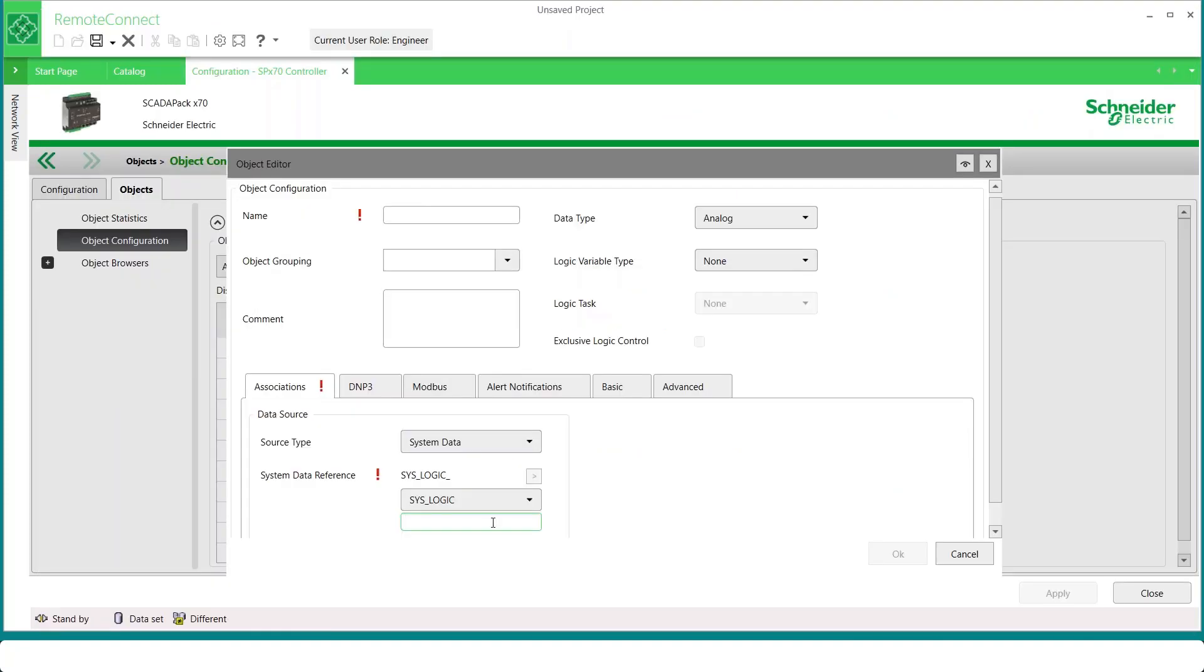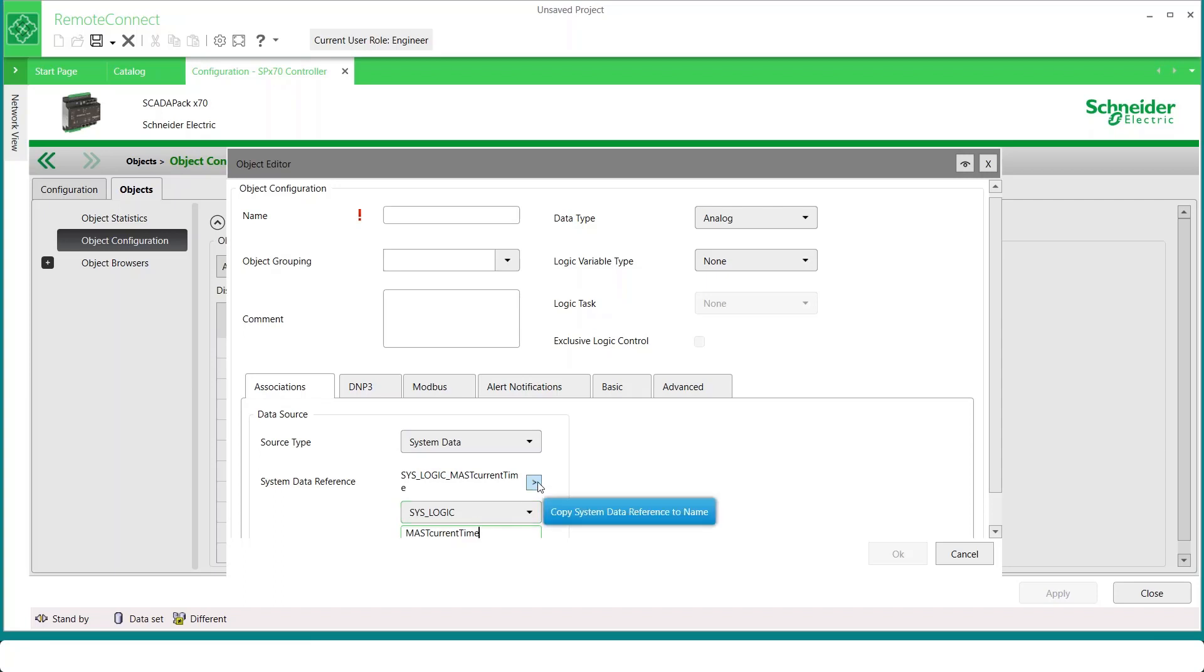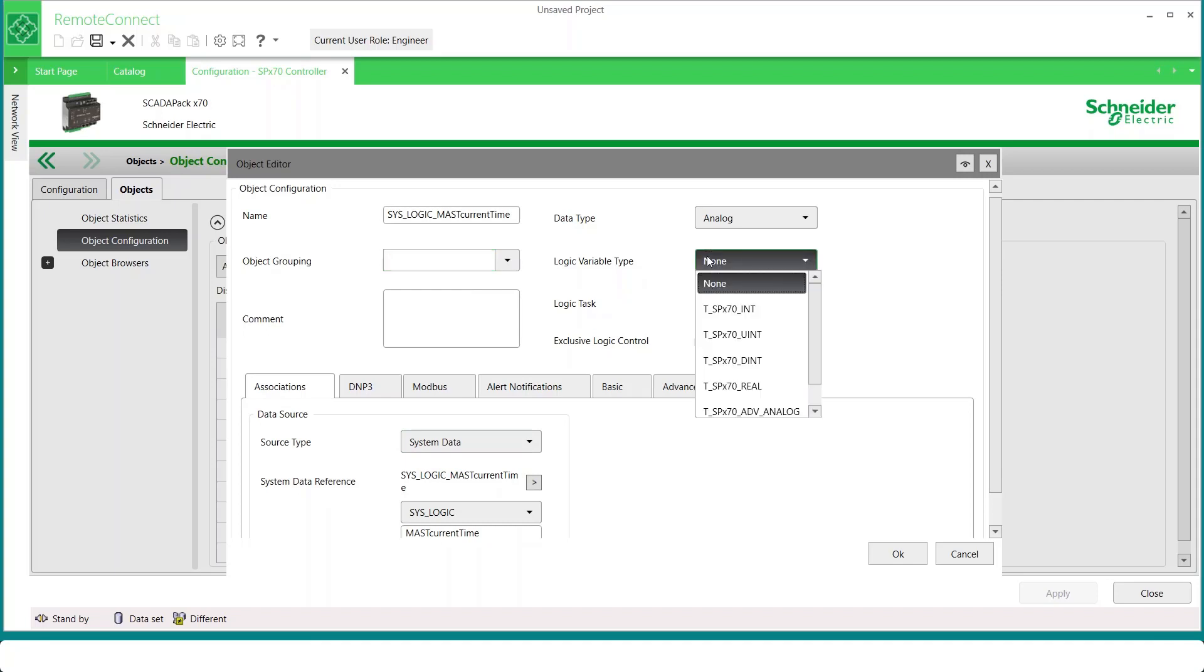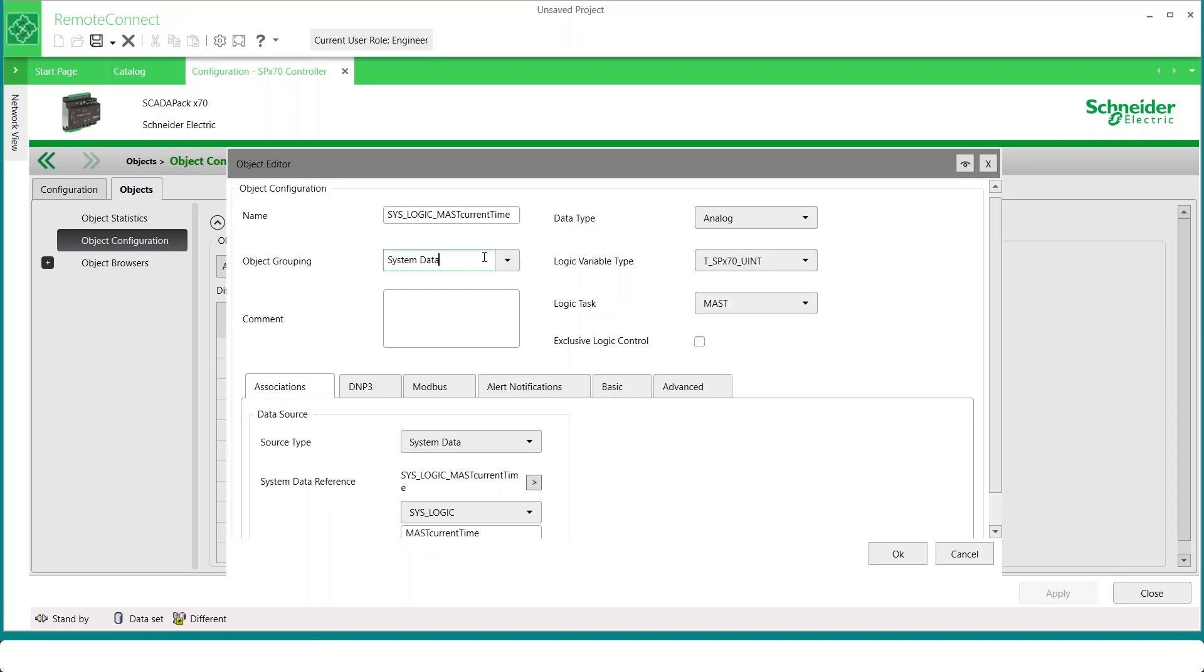Back in the Object Editor, we can now add this name, MAST Current Time. And we can move that up to the name of the object by clicking this button. We would now add it to an object group. And the logic variable type for this one, back in help, it would have told us that this was an unsigned integer. We could then use this status object's value parameter in a logic application.